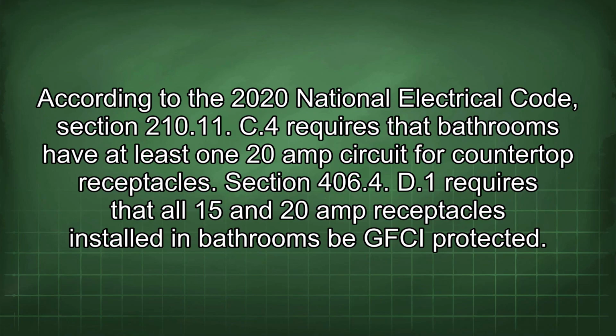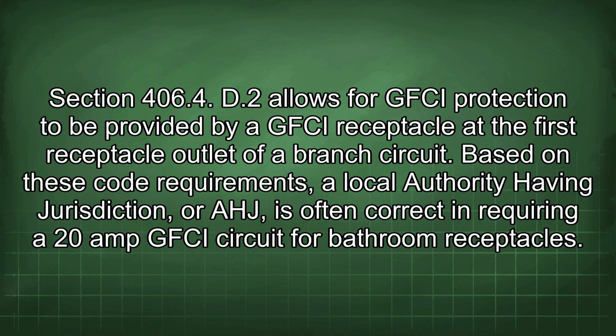According to the 2020 National Electrical Code, Section 210.11(C)(4) requires that bathrooms have at least one 20-amp circuit for countertop receptacles. Section 406.4(D)(1) requires that all 15 and 20-amp receptacles installed in bathrooms be GFCI protected. Section 406.4(D)(2) allows for GFCI protection to be provided by a GFCI receptacle at the first receptacle outlet of a branch circuit. Based on these code requirements, a local authority having jurisdiction, or AHJ, is often correct in requiring a 20-amp GFCI circuit for bathroom receptacles.